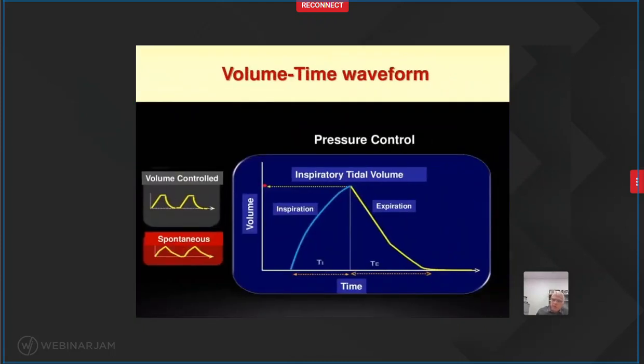Okay, the third waveform is volume. The volume waveform is very similar to the pressure waveform. The main difference is that, again, it depends, the shape of that volume waveform depends on the type of ventilator you're using. And also, the volume waveform starts from zero. It doesn't start from the PEEP, it starts from zero volume, okay? And it should end at zero volume. So the inspiratory volume and the expiratory volume should be equal, should be the same.